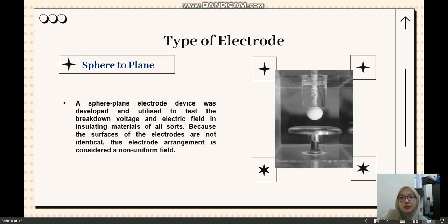Okay, next, sphere to plane. The sphere to plane electrode device was developed and utilized to test the breakdown voltage and electric field in insulating material of all sorts, because the surfaces of the electrodes are not identical, and this electrode arrangement is considered a non-uniform field.